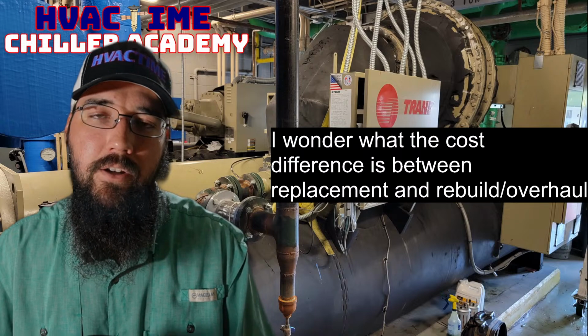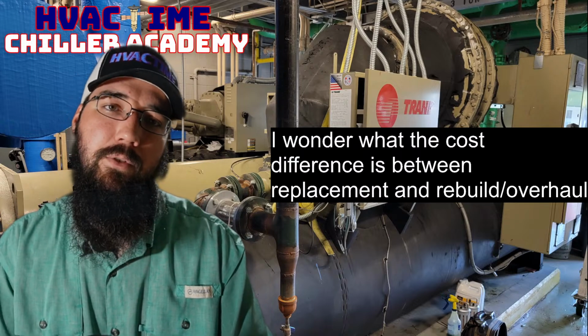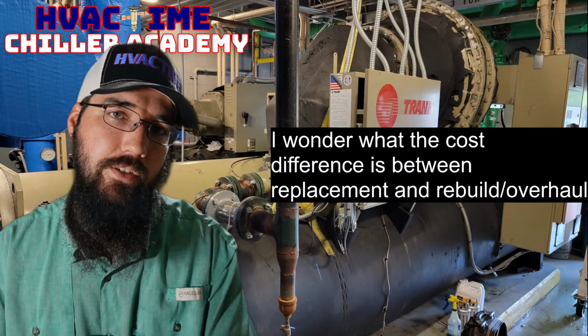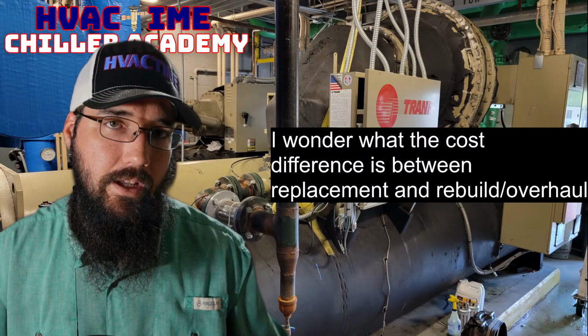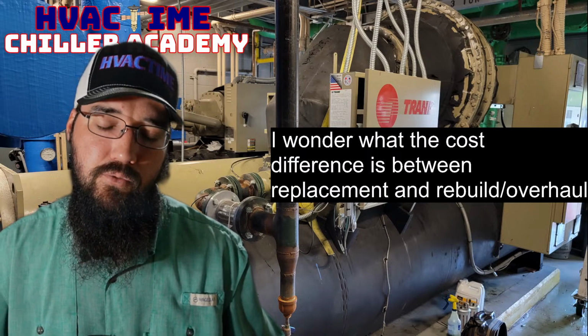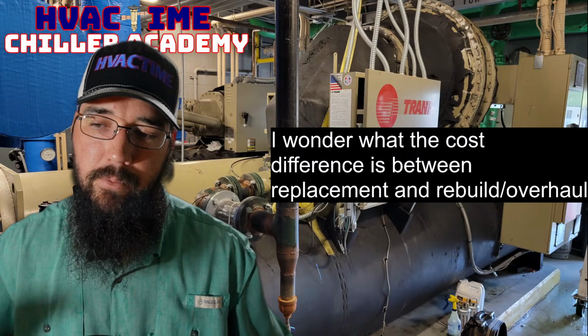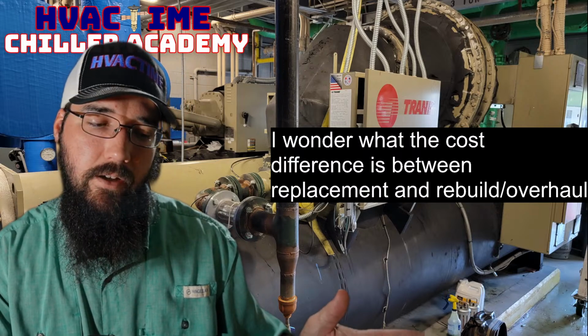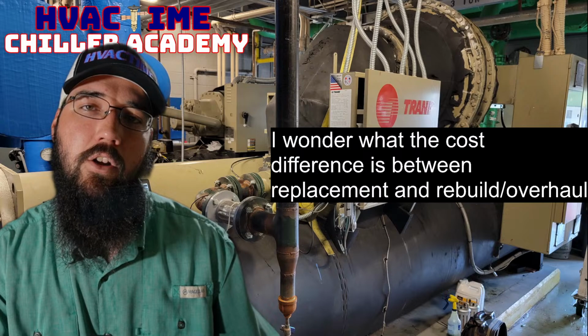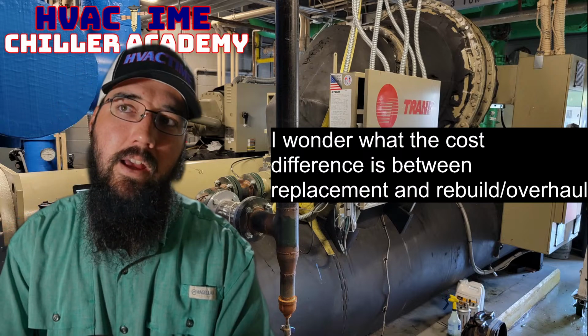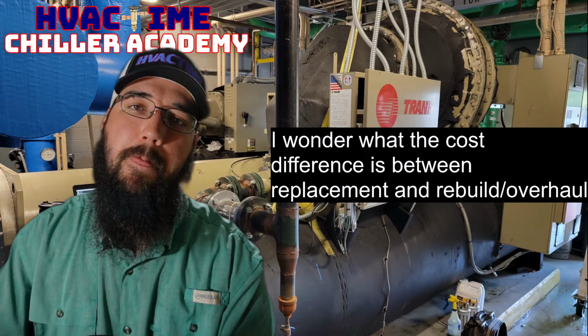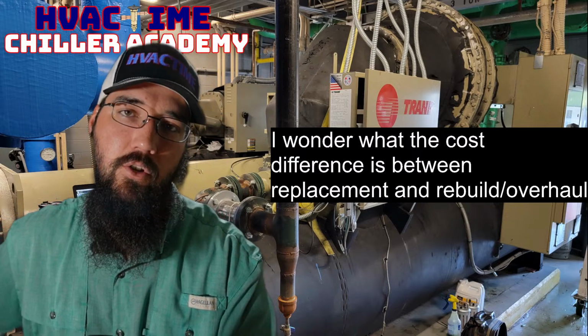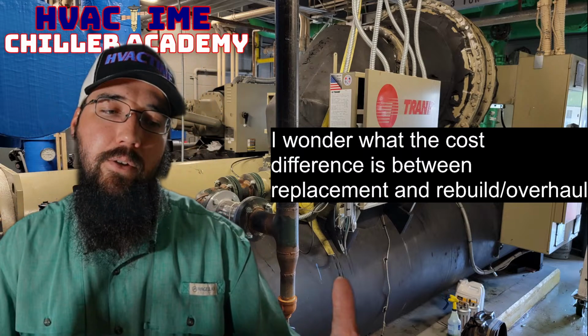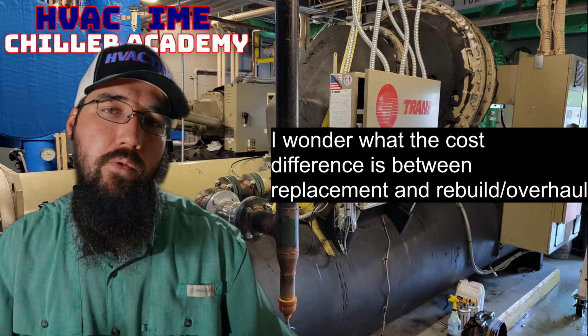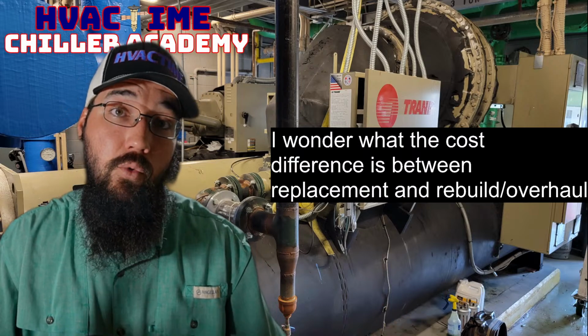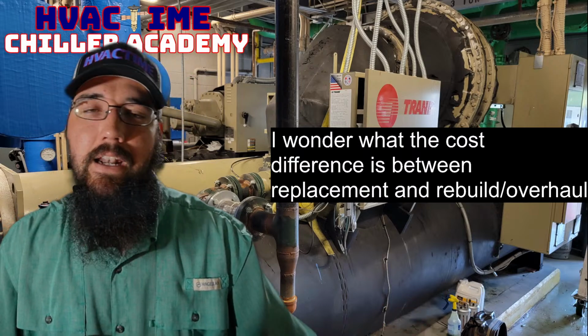So that can be another area that tips that balance between this is worth it versus this is not. But again, the mag bearing side of things, short of the YZ and some of the newer equipment, that's going to be your smaller machines at that, because mag bearings, other than the YZ, haven't really scaled to those larger sizes yet. So the cost benefit and overhaul on those smaller machines is already kind of tilted.